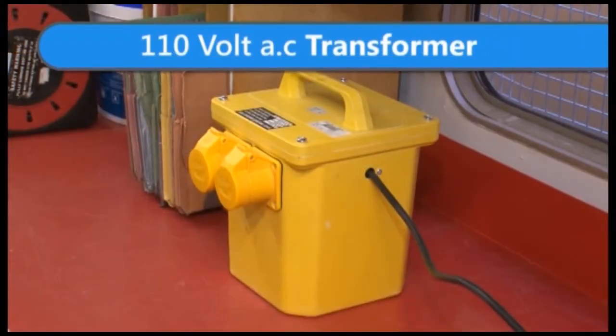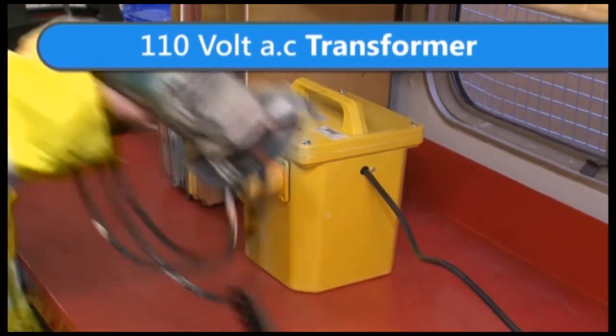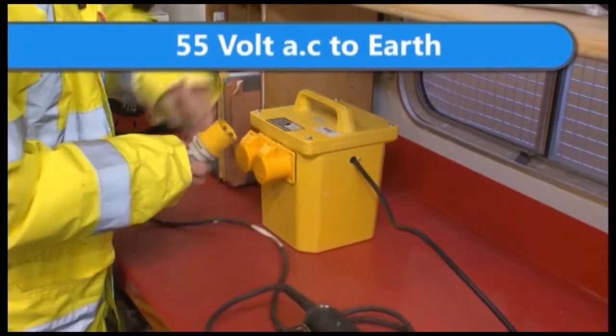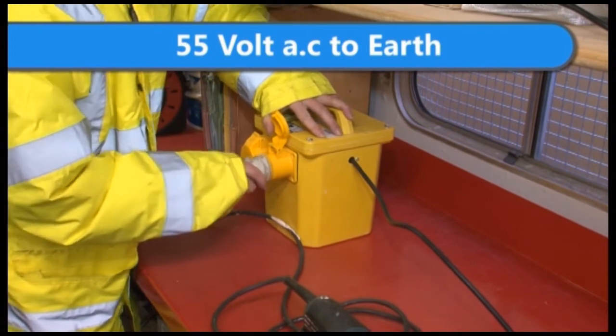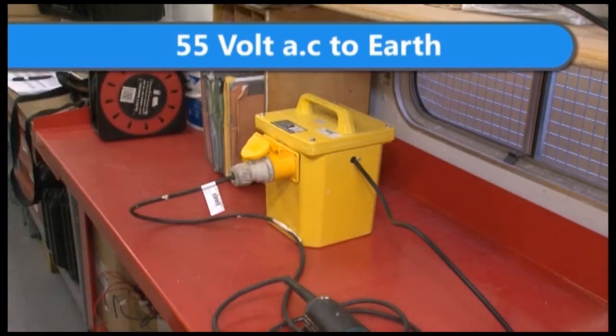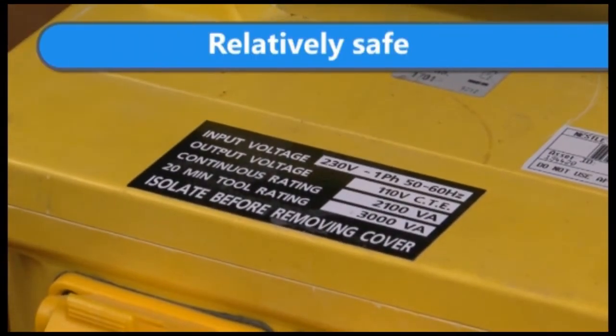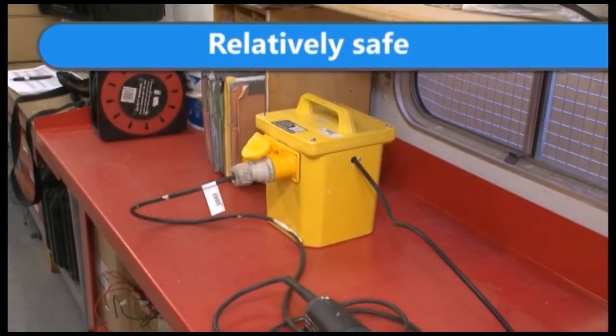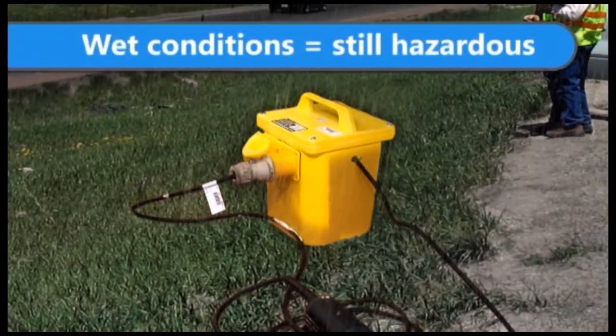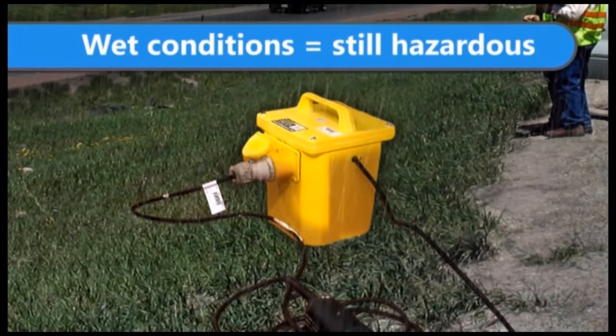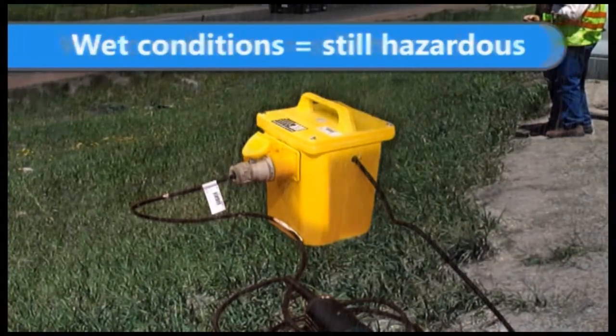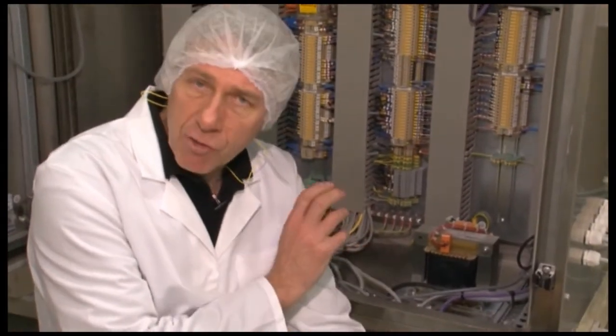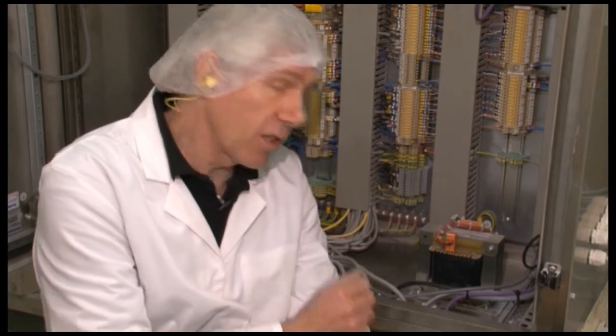A good example of this technique is 110 volt AC centre tap to earth systems, which give a voltage of 55 volts AC to earth. Although slightly higher than extra low voltage, it is still considered relatively safe. But it must always be recognised that in wet conditions, even this voltage could be hazardous. The use of extra low voltage is also useful in equipment which might have to undergo inspection and test live, such as on control panels.